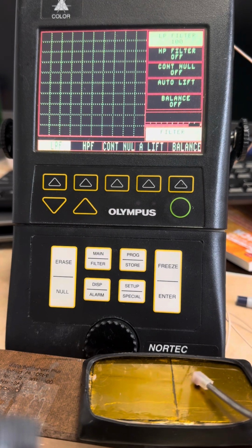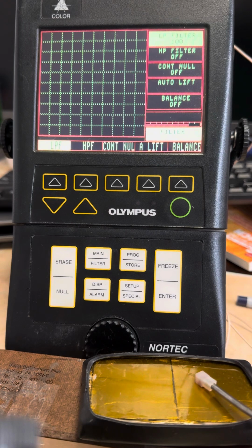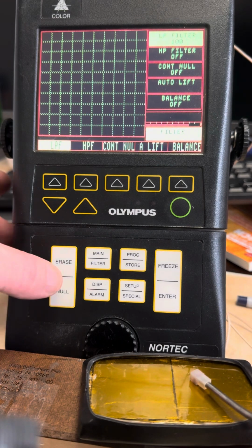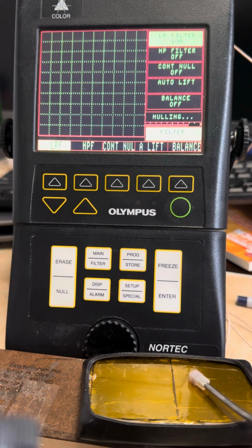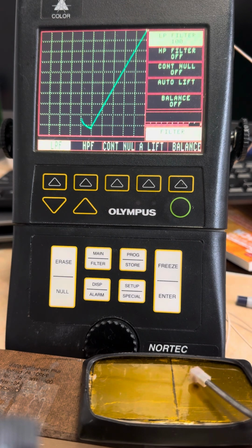Now when I tap the metal, you can't see anything on the screen, so these are default settings. So the first thing we should do is, with our coil on the material, we're just going to go ahead and hit the null button. Okay, that brings the impedance dot on our screen, and now when we lift off, you can see which way liftoff goes. So this is our liftoff line.